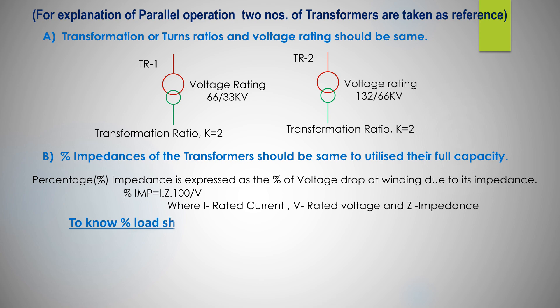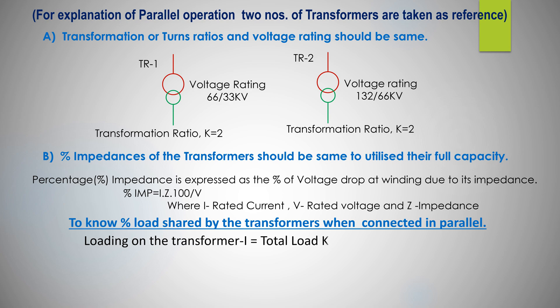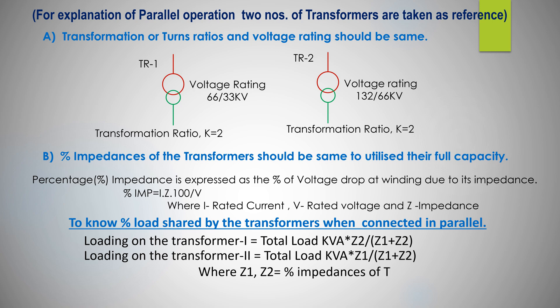To know percentage of load shared by the two transformers when connected in parallel: Loading on transformer 1 = total load KVA × Z2 / (Z1 + Z2), where Z1 and Z2 are percentage impedances of transformer 1 and transformer 2 respectively. Generally, transformer with lower percentage impedance shares more load than that of higher percentage impedance rating.